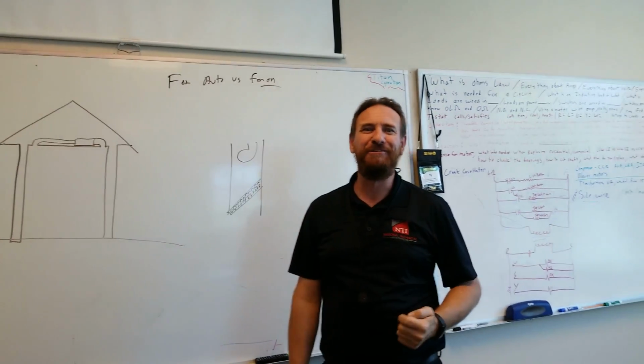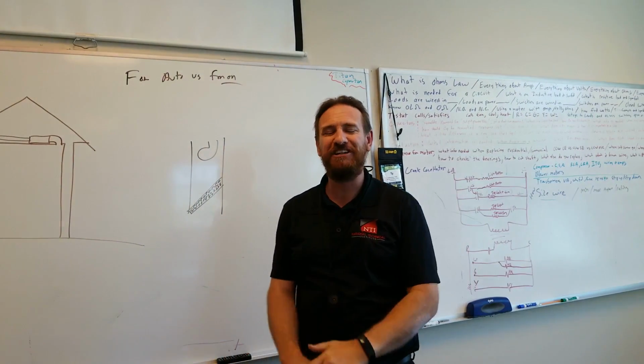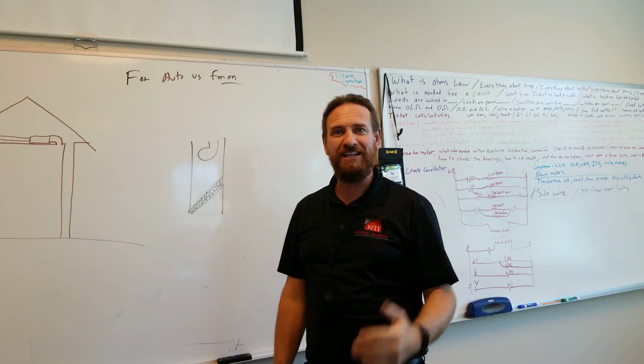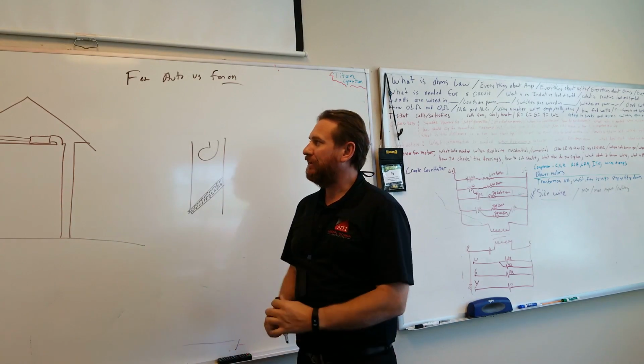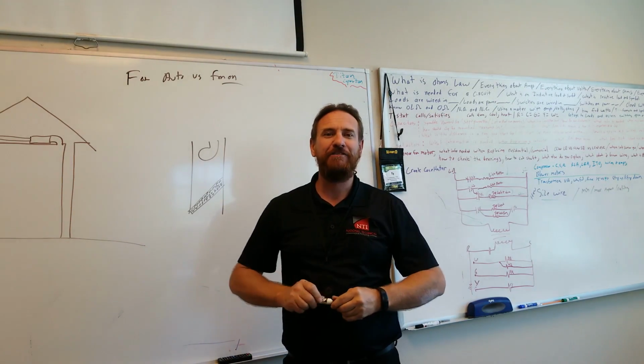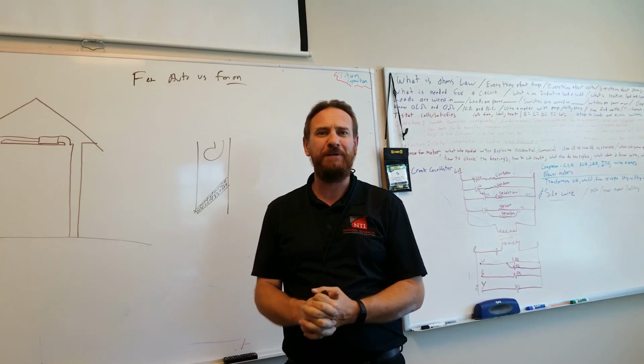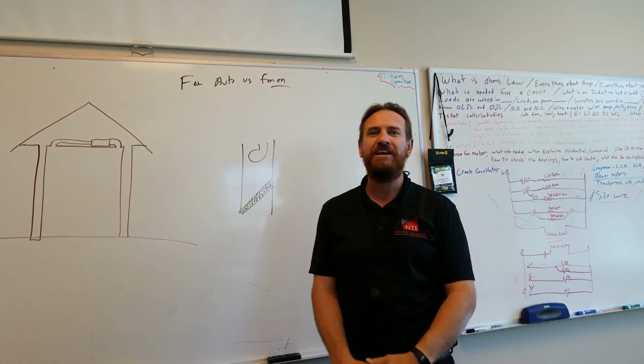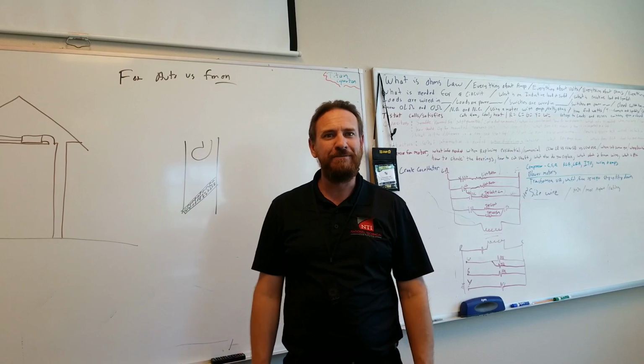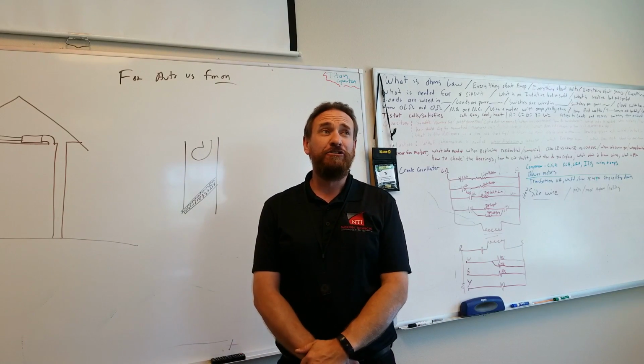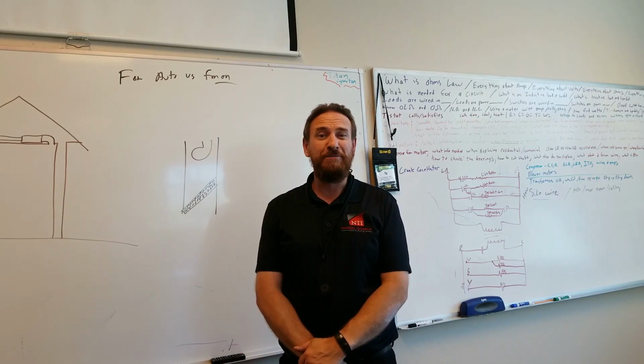It's a loaded question, one of the big debates in the HVAC industry, and it really applies to what needs you have. For one, we have to look at what type of motor you have. If we have the older standard 3-speed permanent split capacitor motors, then that motor is going to use a decent amount of electricity when it goes. So it's moving air, it's using a decent amount of pulling, a decent amount of amps, a lot of wattage going through there.